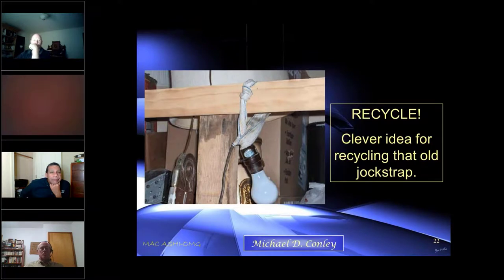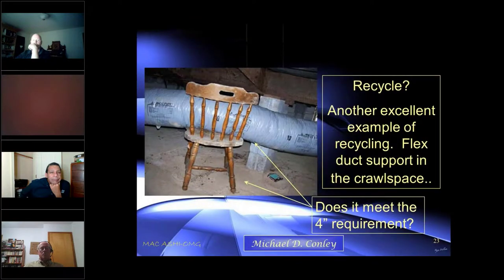Here's a clever way to use a jockstrap instead of letting it go to waste. This is an example of flex duct support in a crawl space — this is actually a mobile home. The mobile home requirement is that duct work has to be at least four inches off the ground, which this is, but that's not the proper support for it.